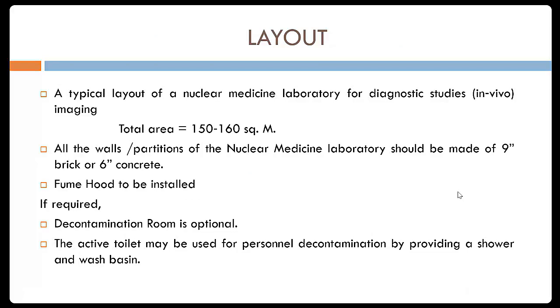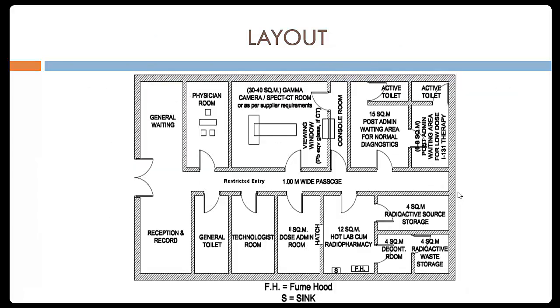There should be an active toilet. Active toilet in the sense, for the person who had a radiopharmaceutical, to wash the face or to go to the toilet and all, there should be an active toilet which should have a shower and wash basin. This is the typical layout for the nuclear medicine department.